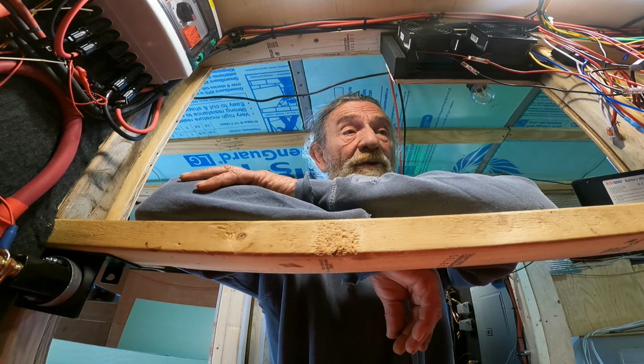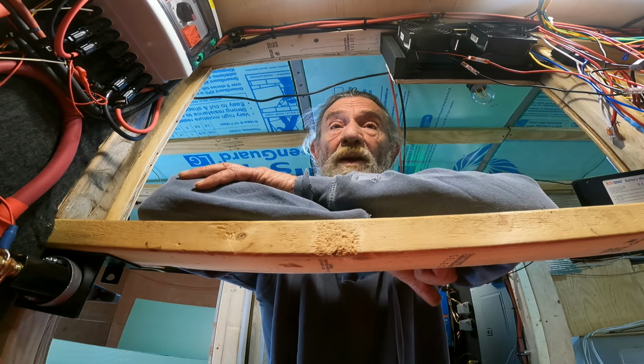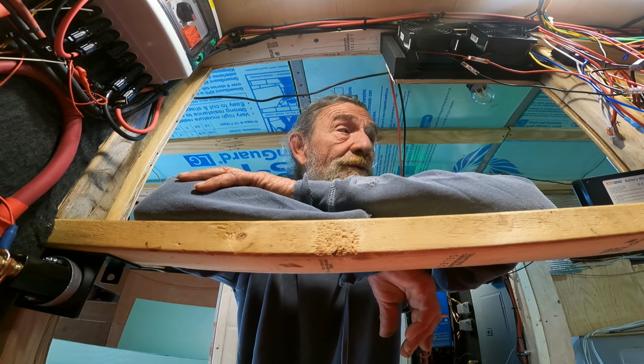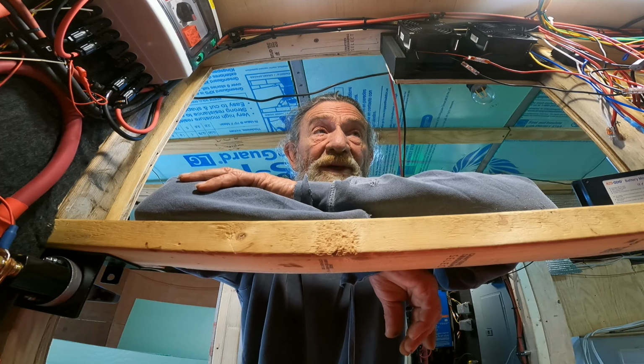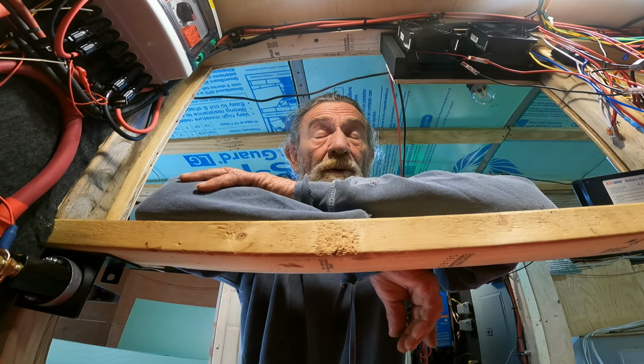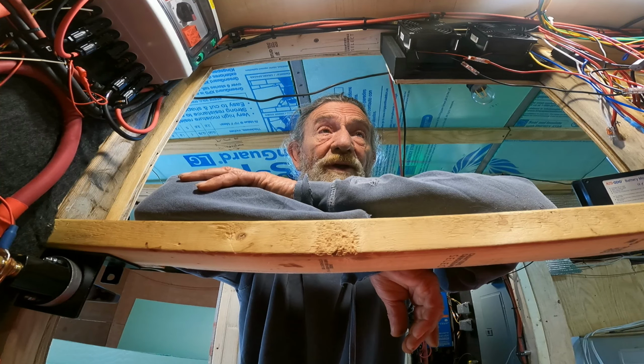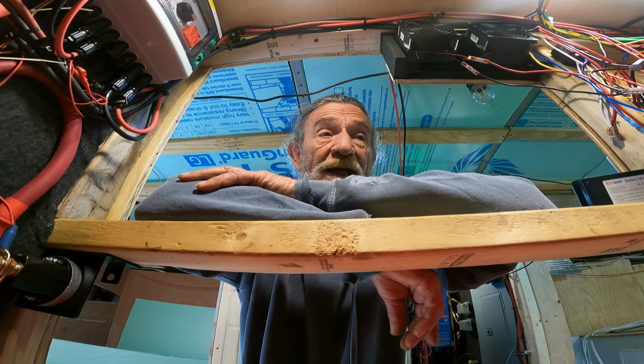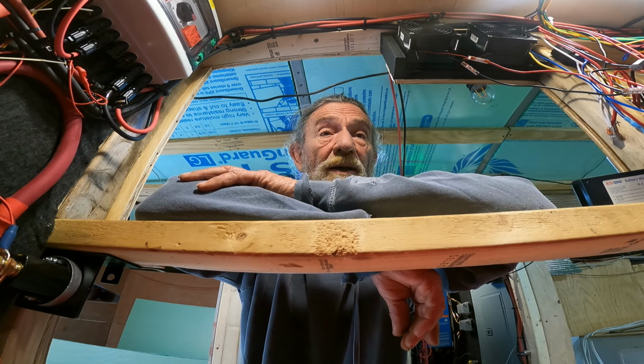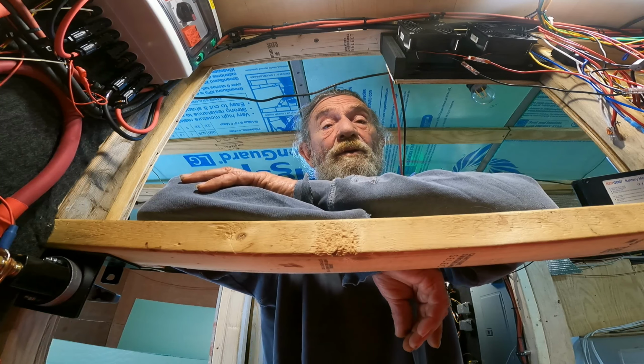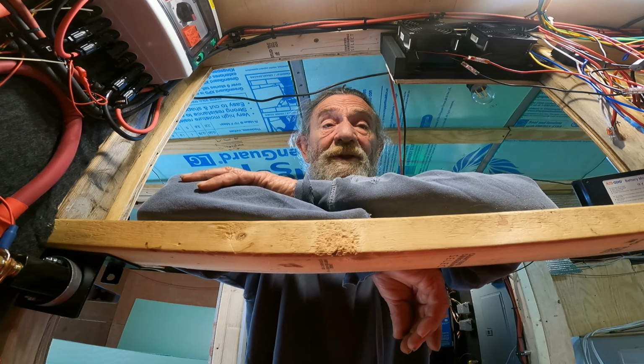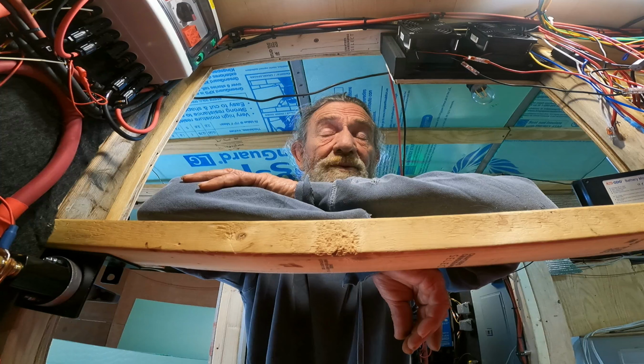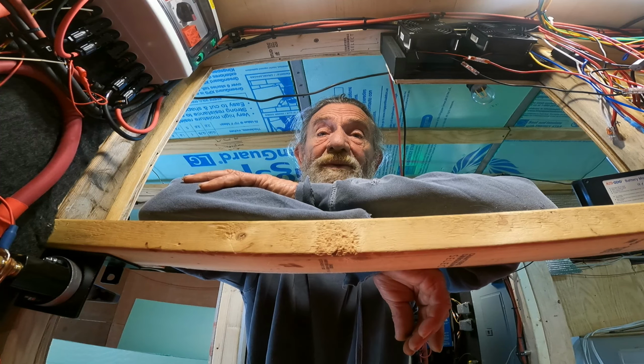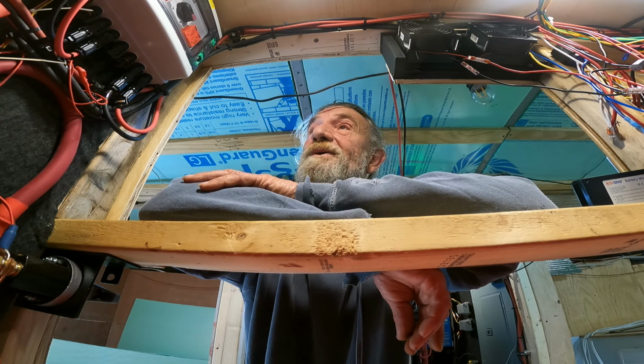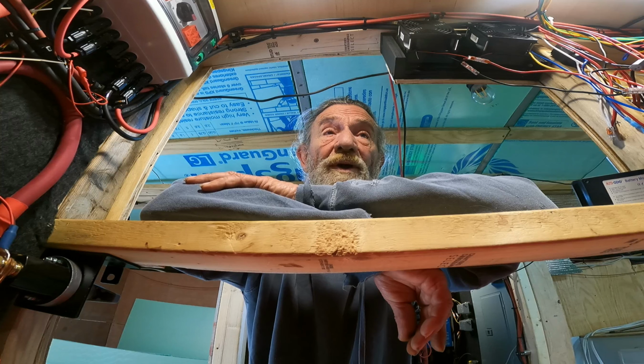When I get the MK3, I'm also going to run a feed cable through a pass-through so I can work and configure the relay on the inverters without having to go all the way into the cabinet. I don't like being inside the equipment cabinet now that I've got power applied to everything. It just makes me nervous. There's a lot of action happening and a lot of power in here, so I wanted to give you a rundown on that.